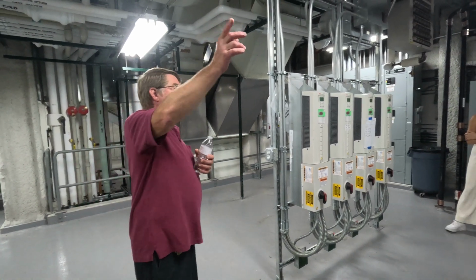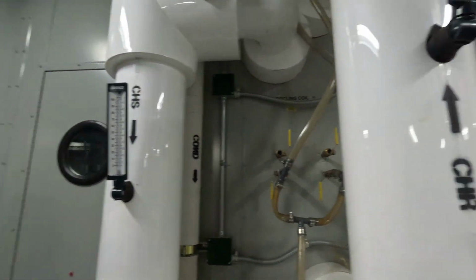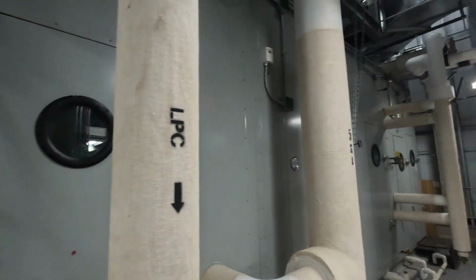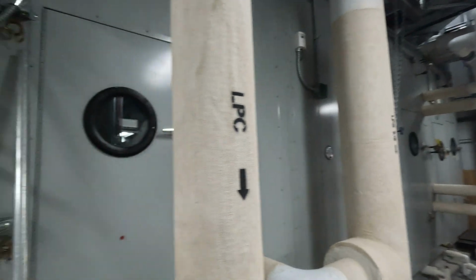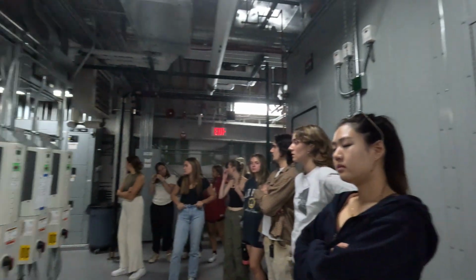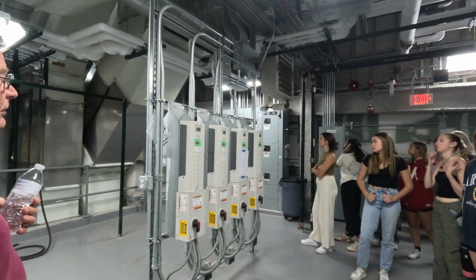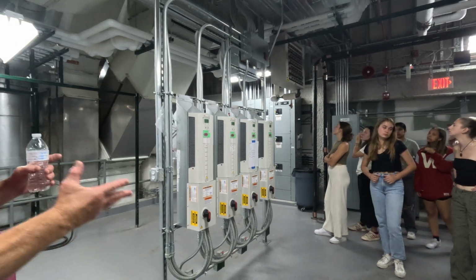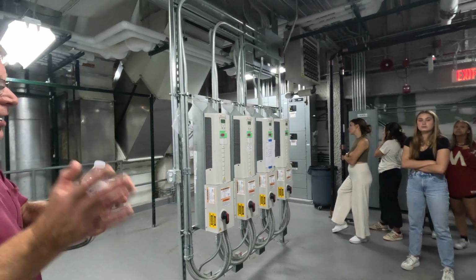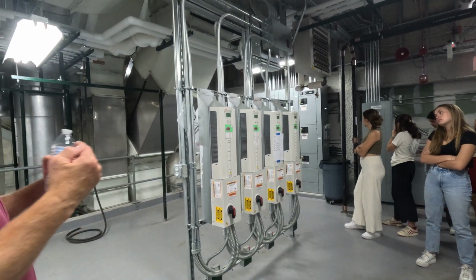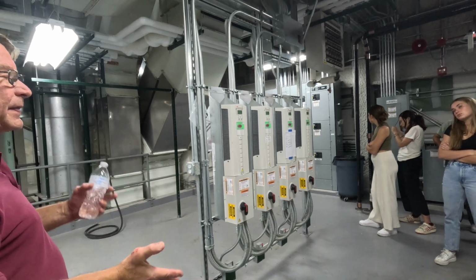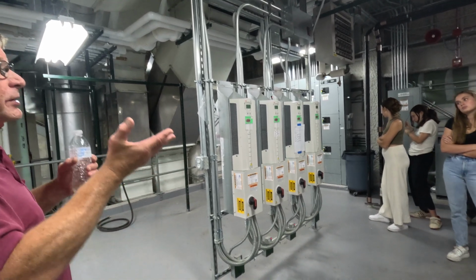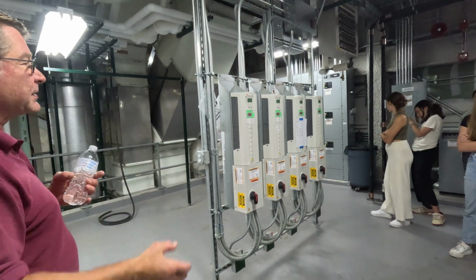So these are air handling units number 3 and number 4. They're the same as the first 2. Now we were talking about the air coming into the building. Now we got to get the air out of the building. So these 4 drives here are for the exhaust fans that are on the roof that we'll look at later on. The difference between that is the air handling units bringing the air in run at about half speed, and that way they can fluctuate as needed in order to supply the building with the correct amount of air.